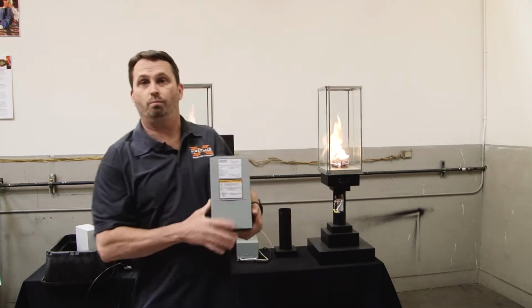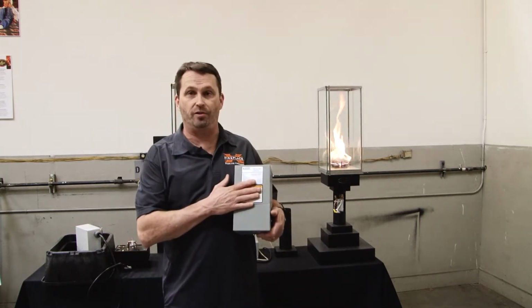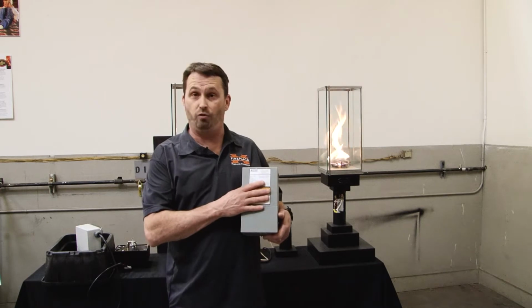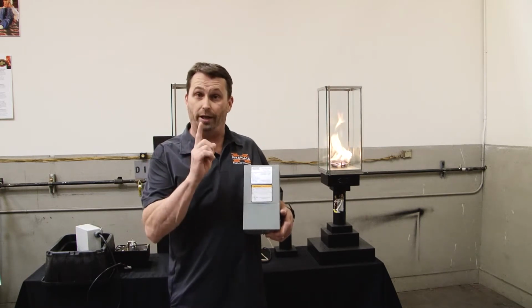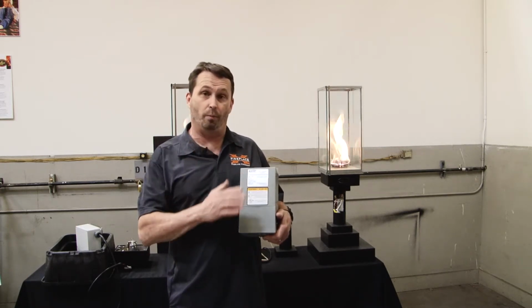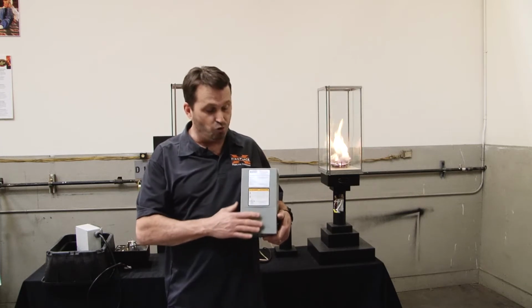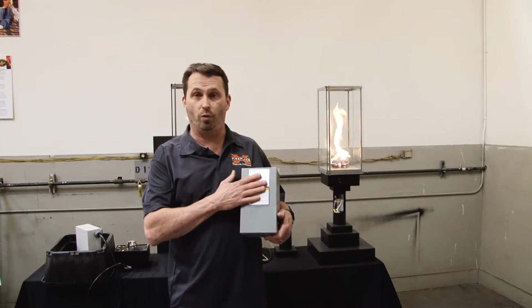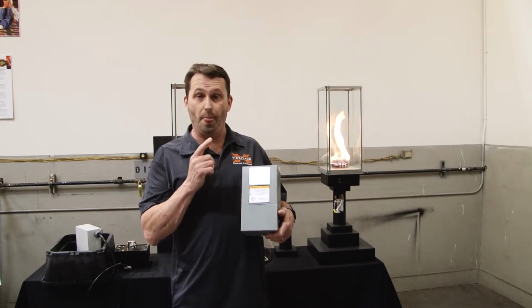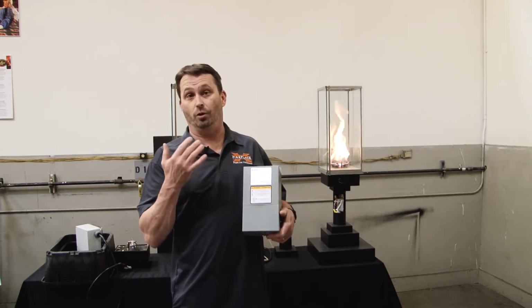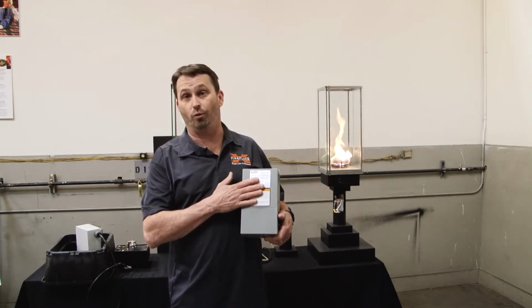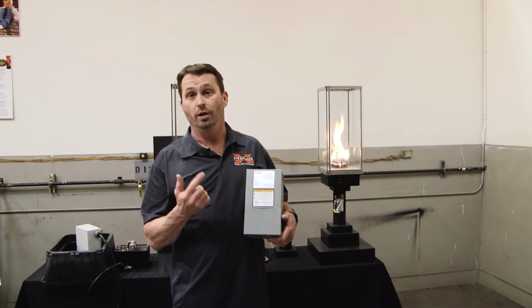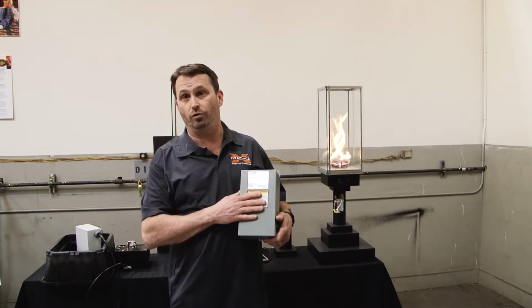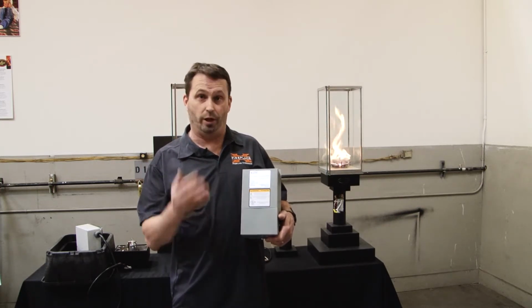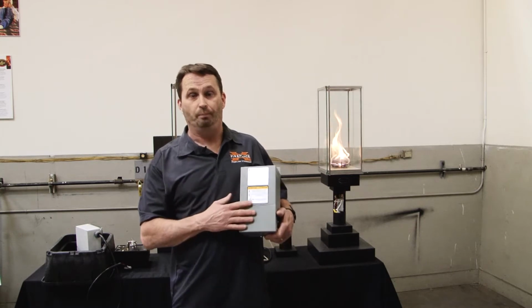We're providing this transformer from Travis Industries. You have to buy this transformer separate. So that's part of the number one thing you need to remember: buy the transformer separate. This transformer will run up to 4 torches on one transformer. You can put up to 7 of these transformers on one 15 amp circuit. So up to 28 torches on one 15 amp circuit, 7 transformers.